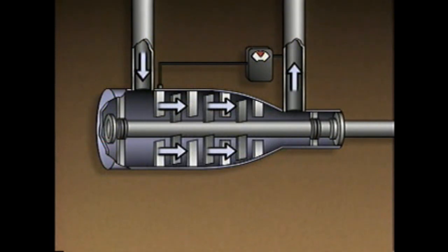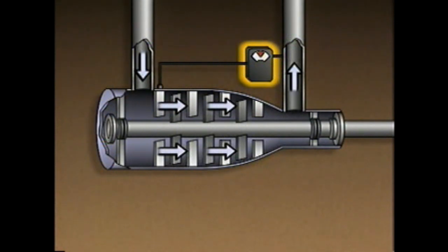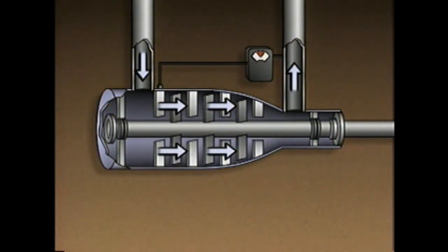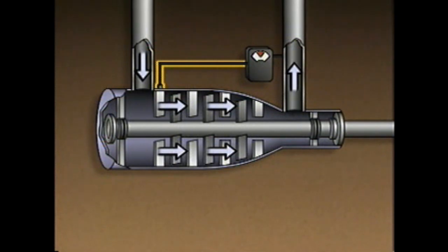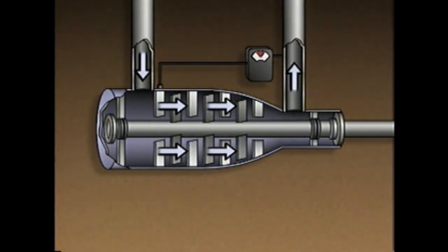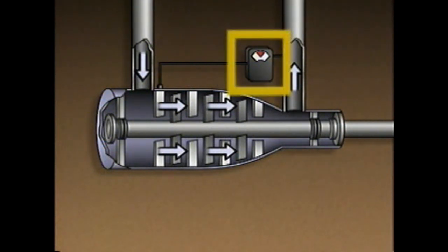The arrows indicate the flow path of the gas through the compressor. The pressure controller has a pressure sensor that senses the pressure of the gas in the compressor's discharge. If the discharge pressure deviates from its desired value or set point, the controller sends a signal that opens or closes the inlet guide vanes.